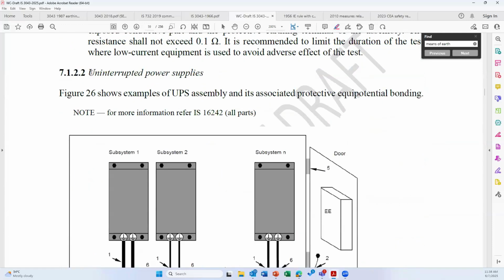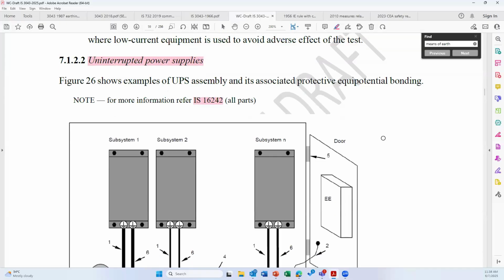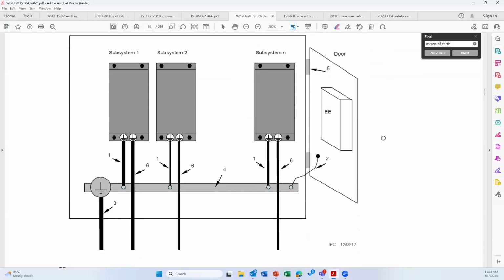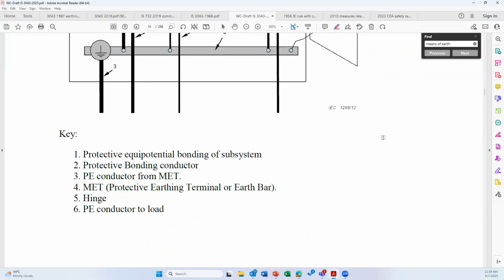Next is UPS. What kind of earthing requirements are available or required for UPS? The source is IS 16242. The idea of including this information into the standard is, of course, these are repeating, but most often the equipment manufacturers try to make their own demands. As a result, the reliability of the electrical installation is highly affected. So this is how the UPS has to be earthed. Big figure copied from the IS standard.